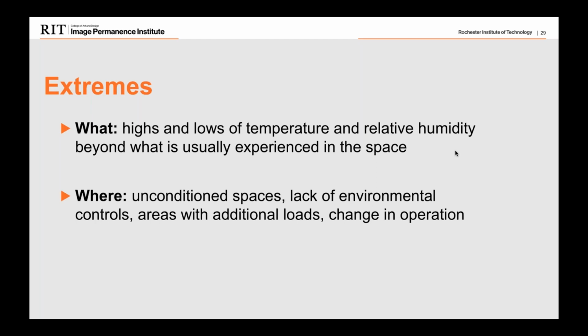Do we keep humidity high all summer versus just for a day or so? These extremes are often present in areas where we don't have as much control as we'd like, or in areas with additional loads—like spaces with natural sunlight creating an unaccounted solar load, or adjacent areas such as atriums or kitchens adding heat and moisture loads not present elsewhere in the collection area. Extremes can also result from changes in operation: a set point changed intentionally or unintentionally, or not changed back, such as with seasonal set points not switched over in time between winter and summer operations.